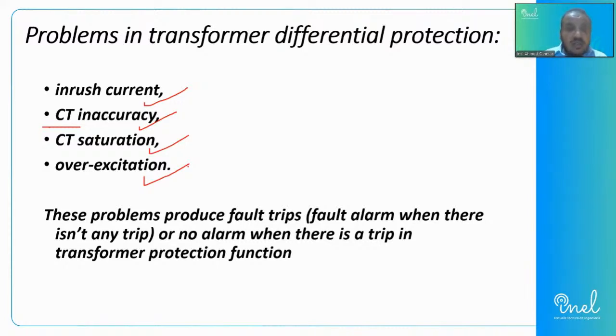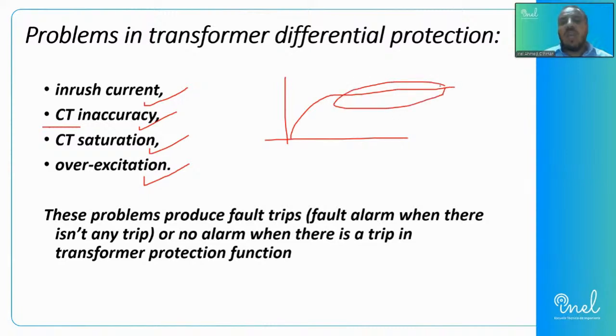Inrush current of the transformer, excitation of the transformer, accuracy of the current transformer, saturation of the core of the current transformer. At the end, each current transformer has a certain core, and such a core is subject to a saturation curve. We have a saturation curve based on the phi to I electromagnetic characteristic or behavior. We have a certain saturation we may face. Those problems mainly produce faulty trips. What is a faulty trip? A faulty trip means maybe there is no fault, but the relay is tripping. That's a fault. Or maybe there is a fault, but the relay is not tripping. So we have faulty trips, either way, whether there is a fault or not. So there is a mal-operation or false operation of the differential relay.